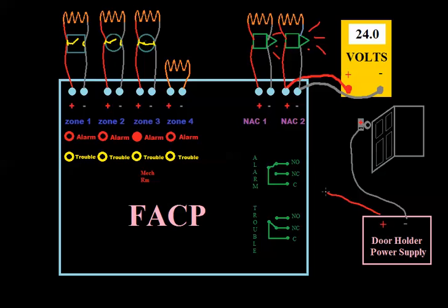So when the panel was in a normal state, if you remember, this common was actually connected to this normally closed. So then I'll come out of normally closed and go here. So in a normal state, this door would be held open all the time. It's going to have its 24 volts or whatever it is. It could be 120 volts for that matter. Either way, you're going to take either the hot or the positive, and you're going to run through this normally closed. So this circuit would be complete if the panel were clear. As soon as it goes into alarm, now this alarm relay opens. Now you can see this positive, it's sitting right here on normally open. It's not going anywhere else besides that. This circuit's no longer complete and this door is going to shut. Now I'm a little bit longer than I like to go on videos, so I'm going to end this one here, but we'll pick this up. We'll probably get into a little bit more on relays. I'll see you in the next video.